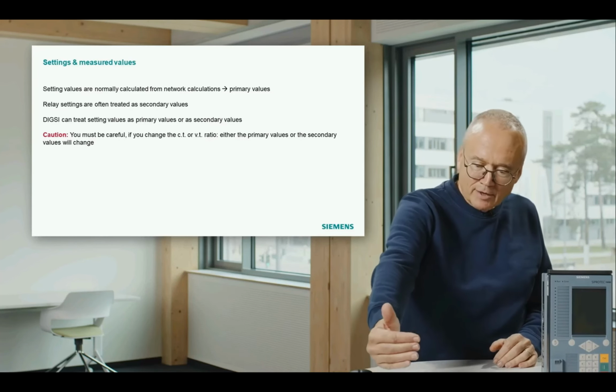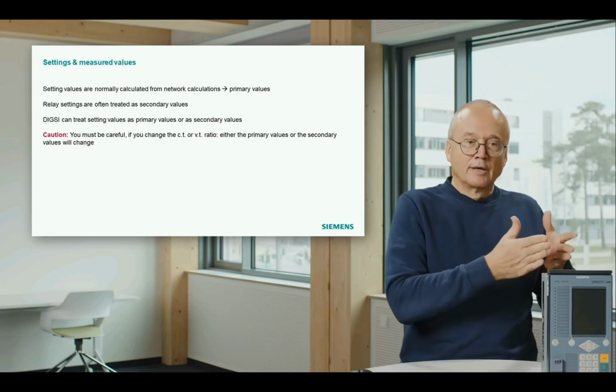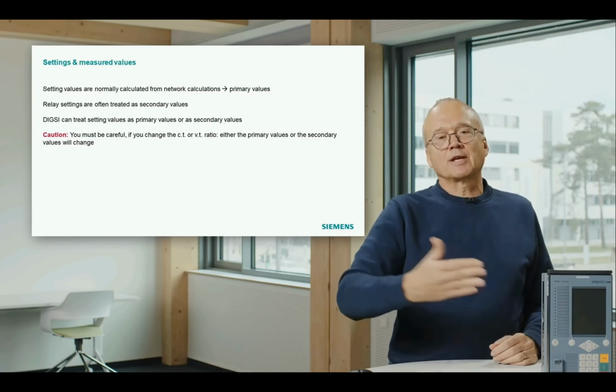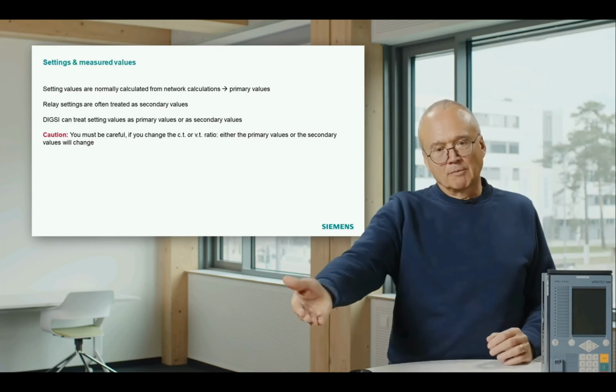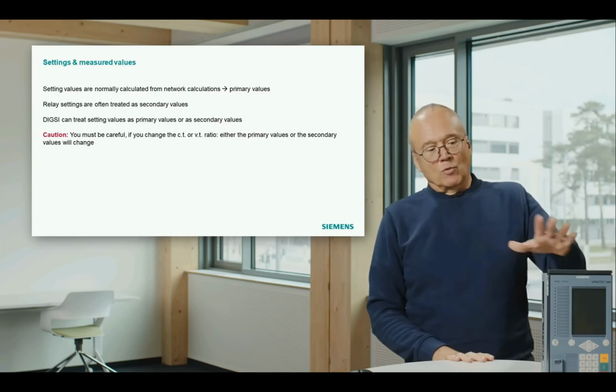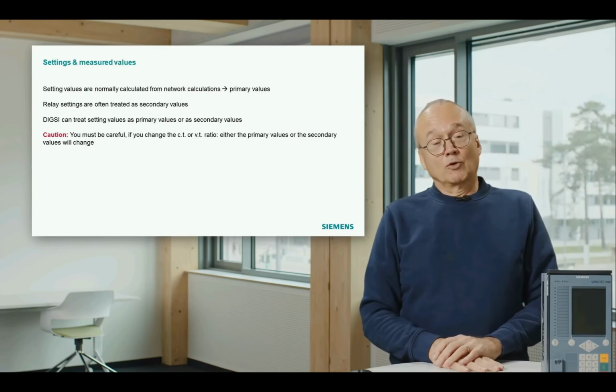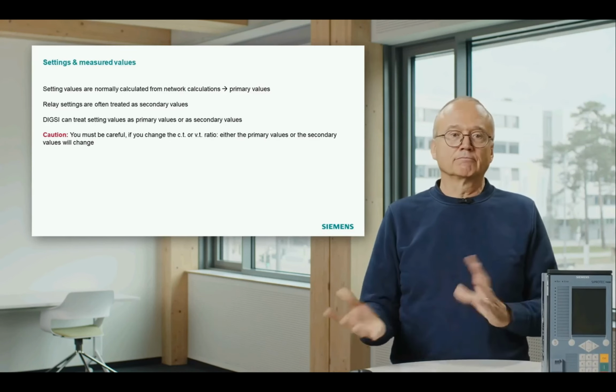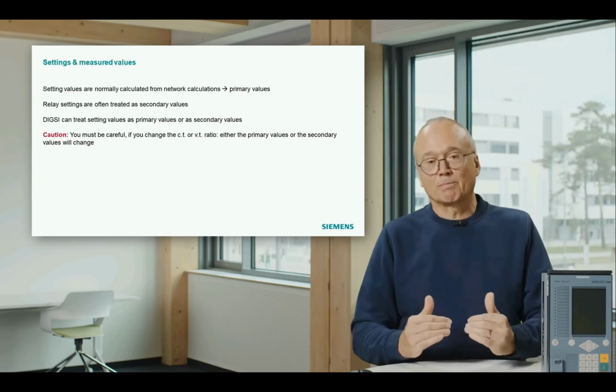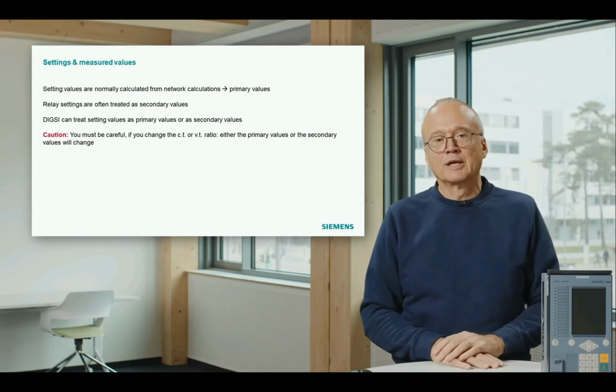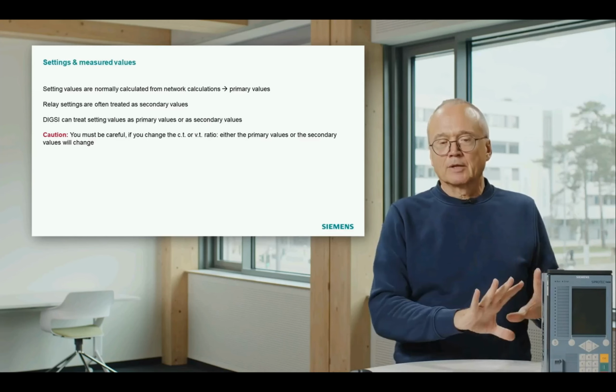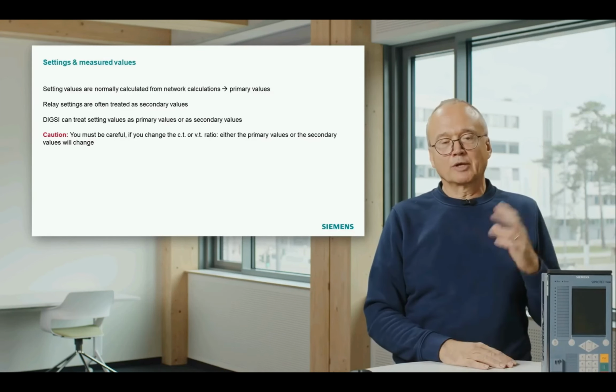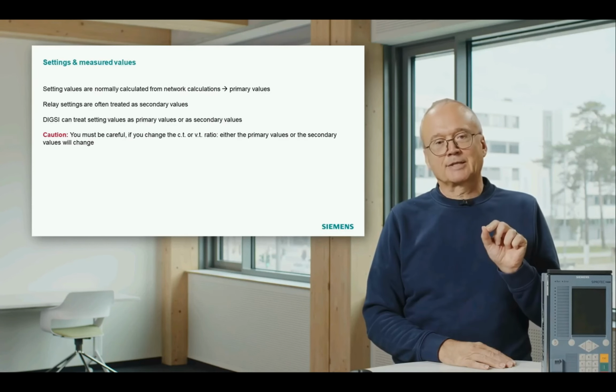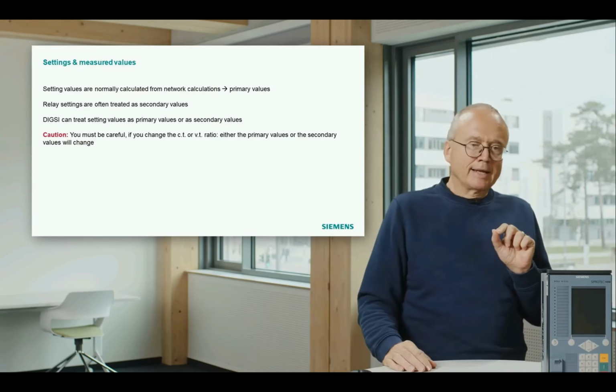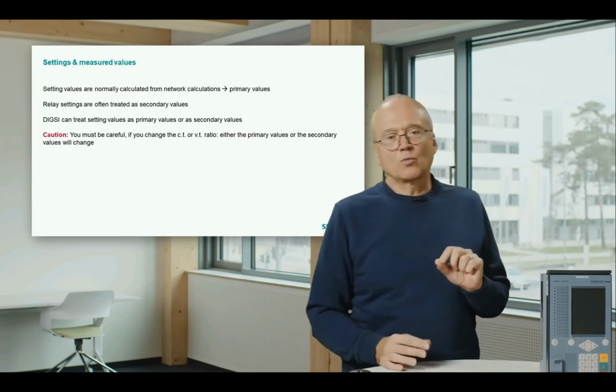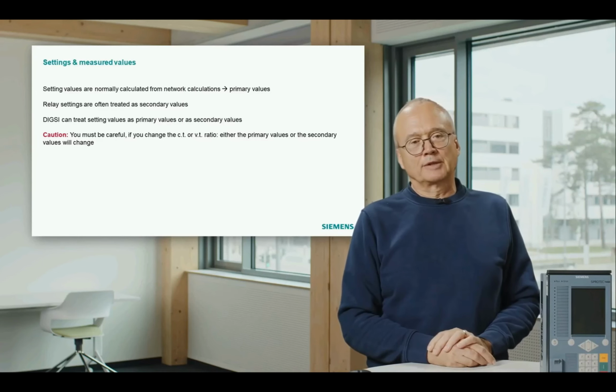That means on this way, from calculation of settings to bringing the settings into the relay, you must somewhere do the conversion from primary to secondary. With digital relays, that has become, of course, much easier, as a PC program can be used using the primary values. That means it can do the conversion. So part of this conversion can be assigned to a program or even to the relay itself. But nevertheless, you must be careful. And there are 2 points where, according to my experience, often problems occur.